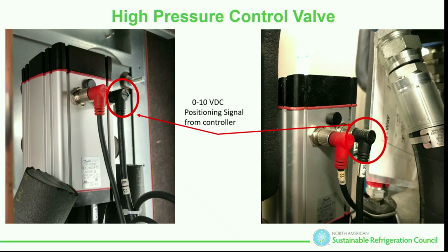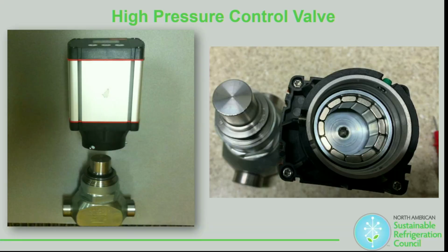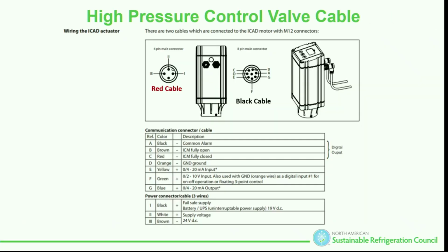Well, I'm pretty lazy, so instead of taking the thing apart and looking for a butt splice or a bad terminal, simply disconnect the black cable. Oops, there's a magnet. Simply disconnect the black cable, go to D, which is ground, F, which is green. You know those needle kind of probes you can put on your meter? Could you not take that off, put your meter on F and D, and simply look for that 0 to 10 volt signal? Look at your drawings, look at your cut sheets, look at the things that you can do, because this is in the manual. What can I do to prove out?